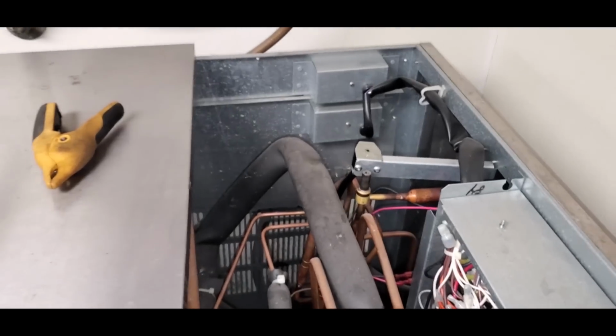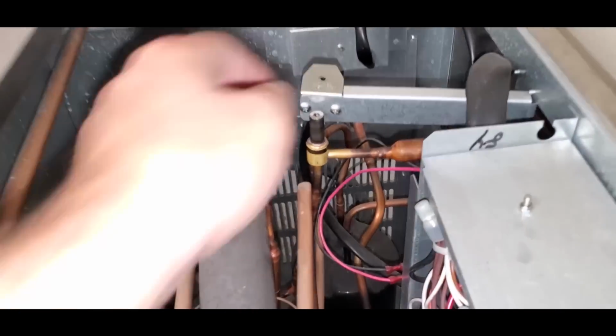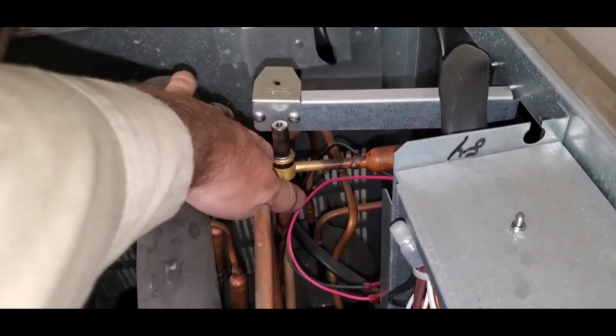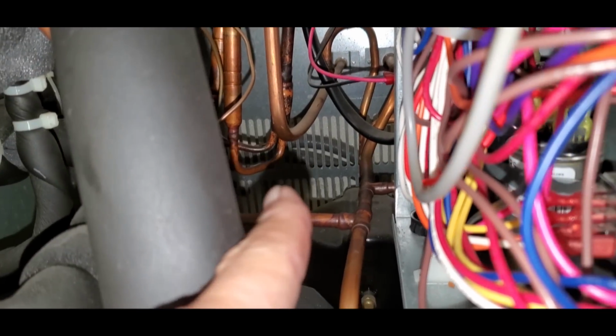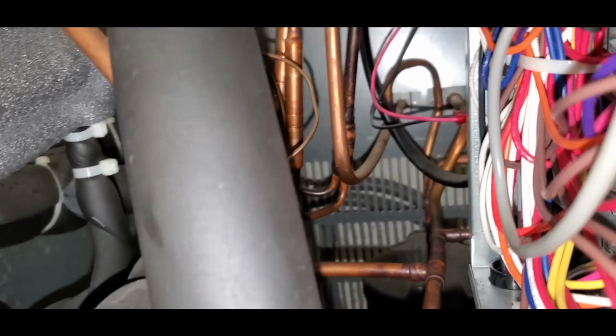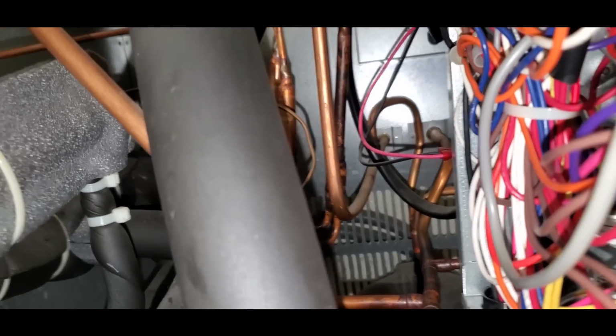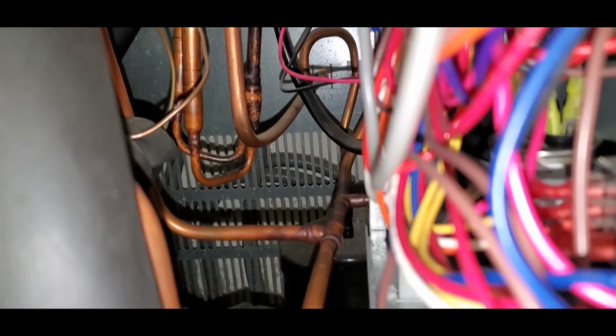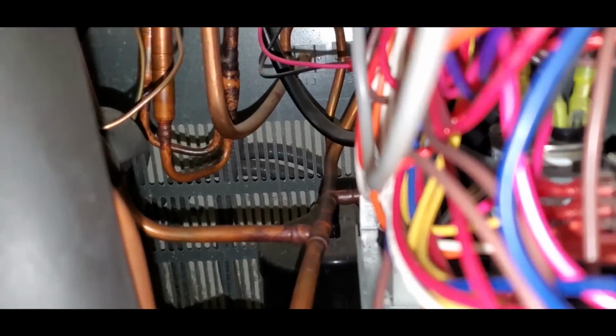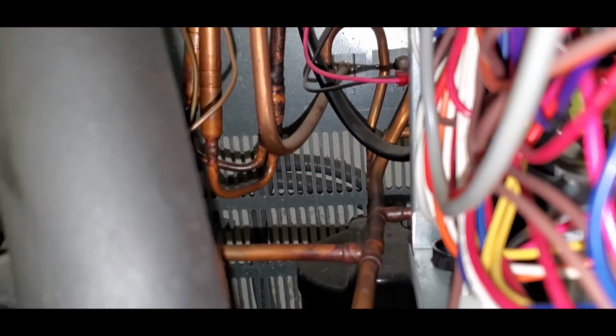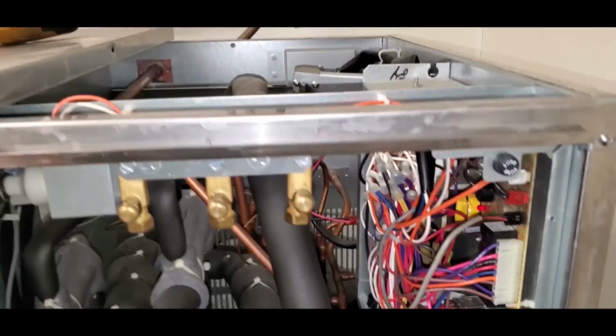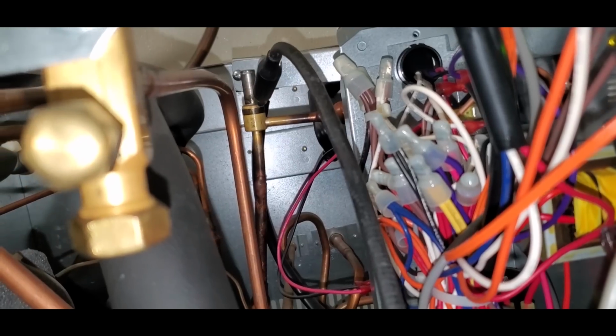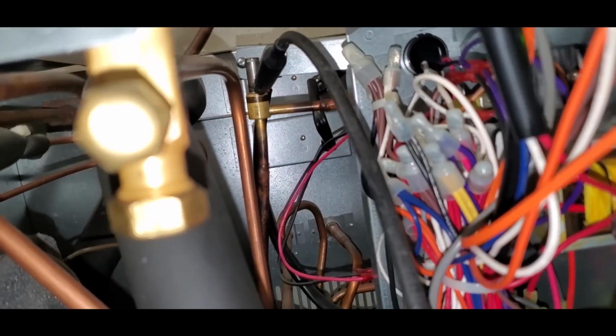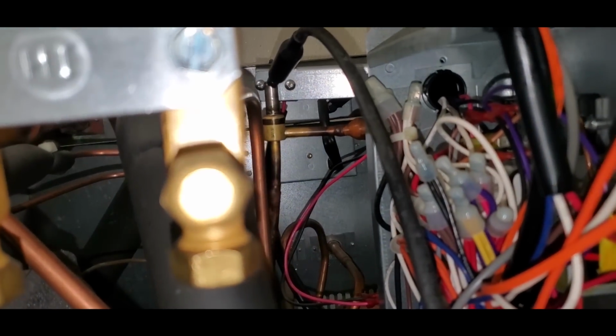Again, I'm just kind of taking guesses here, and so I'm investigating the hot gas valve, and it doesn't feel like it's bypassing. It doesn't feel it's leaking by, but I will say, if you look at the bottom of those hot gas lines right there, there's oil on them. Looks like there might be oil, and there was a droplet a minute ago that I grabbed with my fingers. Right back in there. So, I'm going to do a quick leak check. See if we've got a refrigerant leak possibly on that hot gas valve. So I'm checking the hot gas valve, and I'm not getting a leak, but there's oil all over it, so it's got to be there.